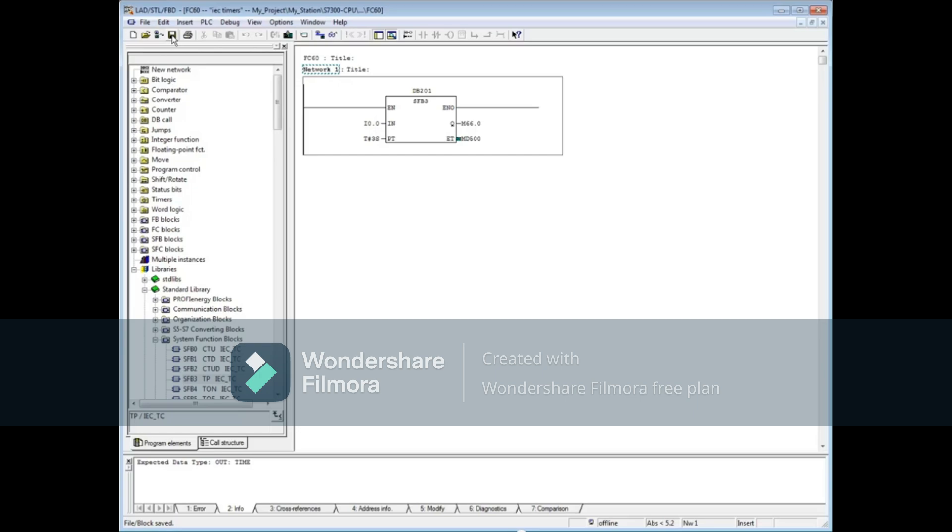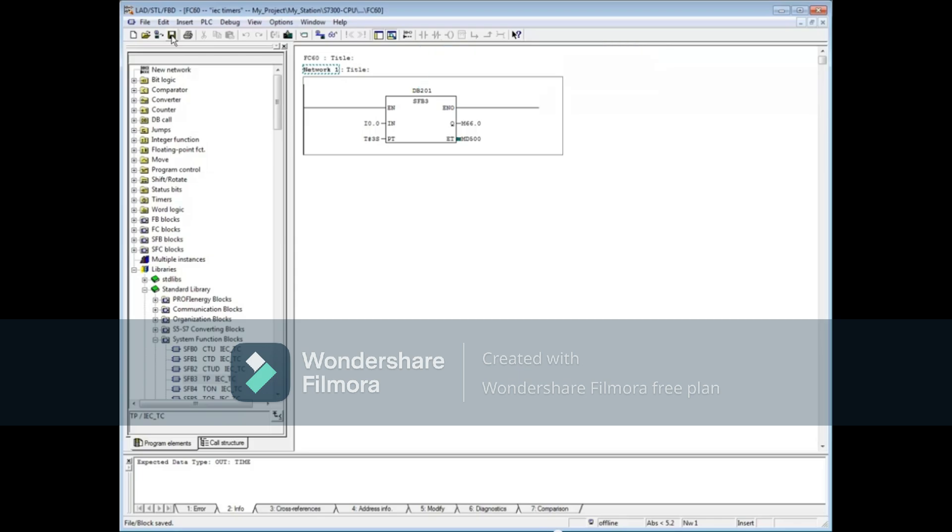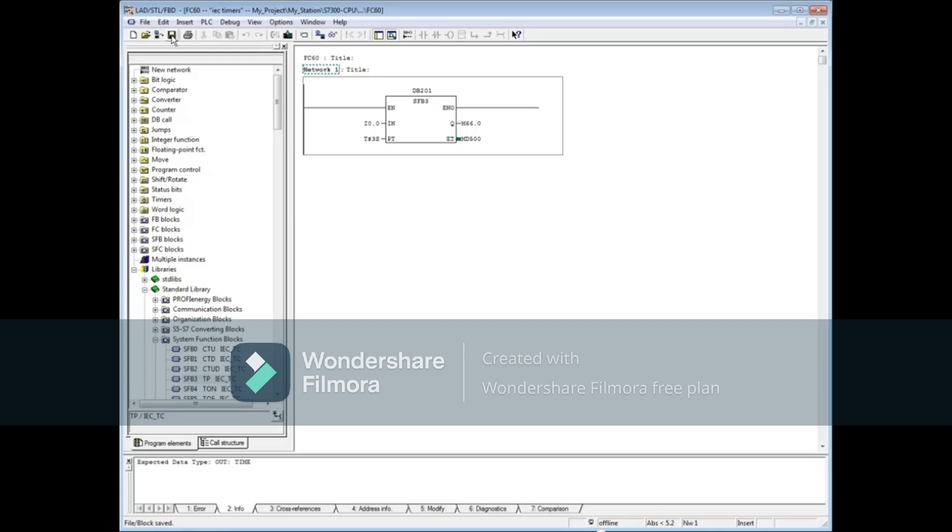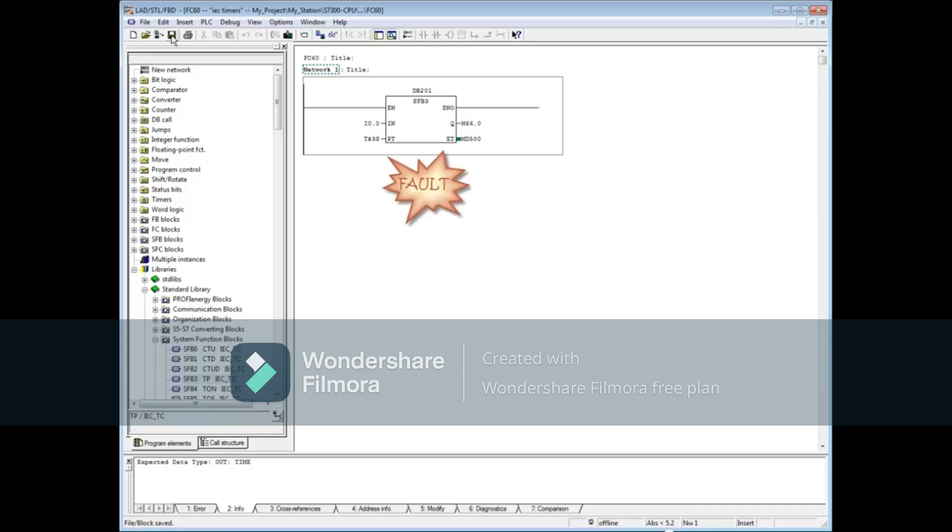Before downloading FC60, we need to be careful to make sure that data block 201 is downloaded first. All system functions and system function blocks are preloaded in the PLC's ROM and do not have to be downloaded. When FC60 gets downloaded, it will call SFB3. SFB3 will in turn call for DB201. If DB201 is not in the CPU, the processor will fault.